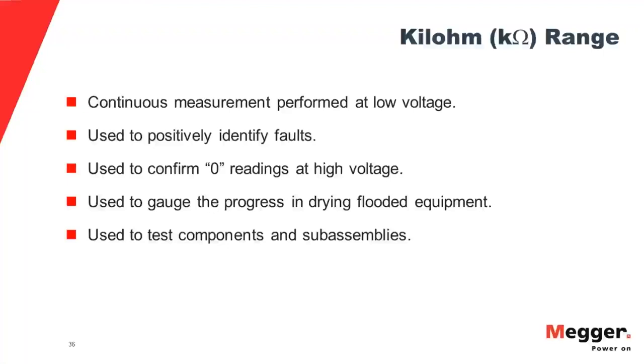And the kiloohm range now, again, this is a range that's intermediate between your continuity and your megohms. Here you're measuring in thousands of ohms. And again, this is done at low voltage, usually maybe 3 volts or something thereabouts. And it has some very vital functions. Not all testers have a kiloohm range, but in many cases you want to make sure that you get this. For one thing, it verifies a faulted test item. So you can hook up and run a test, and you run on a megohm scale, and you run off the low end of the scale. There's a fault on there somewhere. Well, it's nice to be able to switch to another range and actually read it and see what it actually is. That gives you something to work against.